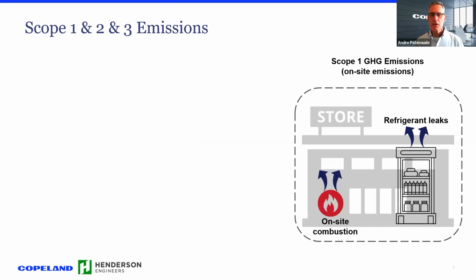So we wanted to look at all 3 types of emissions, and the one that's closest to us in refrigeration that we hear about all the time, of course, are refrigerant leaks. And a real simple one, you got a 2,000-pound 404A system that leaks at 20% a year. When you do the math, that's 713 metric tons of carbon emissions only from the 404A. If you change that to CO2, that same amount of 20% on 2,000 pounds ends up being 0.18 metric tons. It's a significant reduction. There's no doubt about that. And of course, you've got on-site combustion, so gas burning off produces an emission.